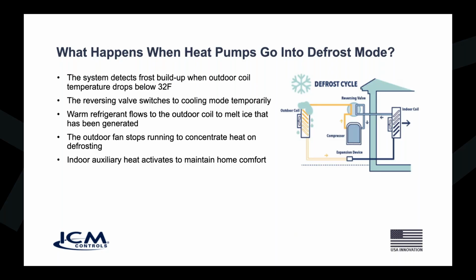Typically, we try to stop the outdoor fan when we are in defrost mode because we don't want to push any more air past the coil. We want it to get nice and warm and melt that ice right away. Some heat pumps will also have auxiliary heat strips built into them, so that when it goes into this defrost cycle and makes your heat pump an air conditioner, you certainly don't want to feel cold air blowing on you. So it turns on a set of auxiliary heat strips so that you don't even know it's gone into its defrost cycle. You just keep feeling warm air coming out of your heat pump.